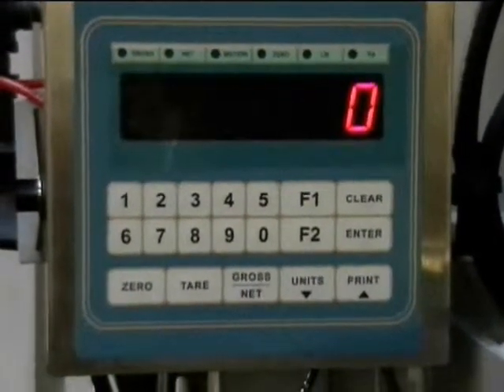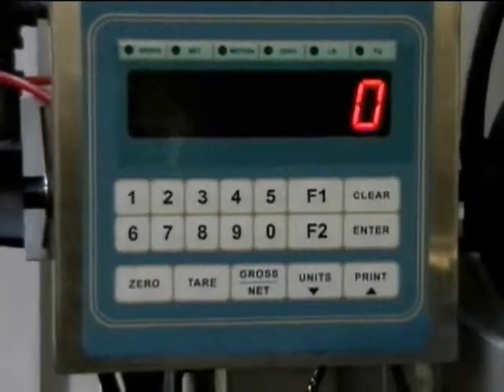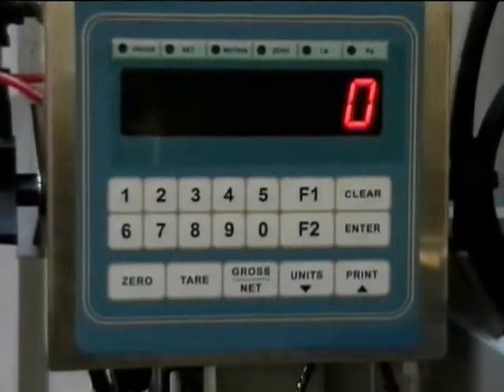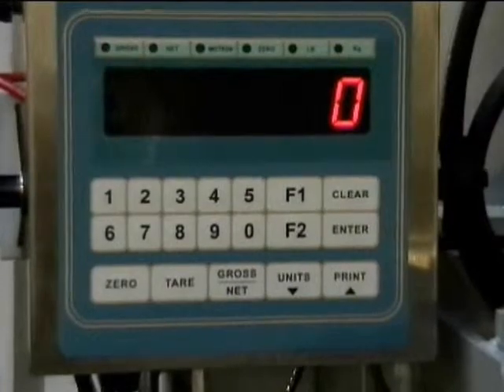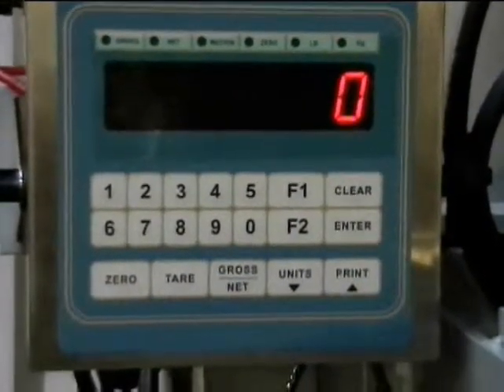For example, if you are filling a 50 pound bag, you may want to enter 45 here. So at 45 pounds, the machine will switch from bulk filling to dribble filling.